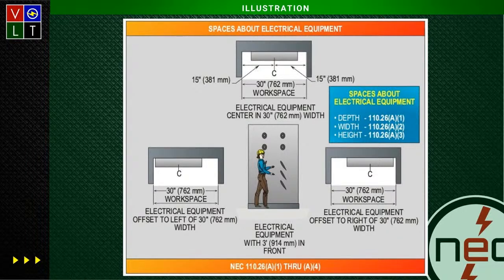I argue this all the time, and people say, 'Oh, I have to work it energized, Willie.' Okay, well guess what? Anything I do in the electrical industry, you could test with a meter while it's de-energized. If you can come up with one example where it has to be hot and you can't test it with a meter, I'm telling you, you don't know how to read your meter. That's my position.